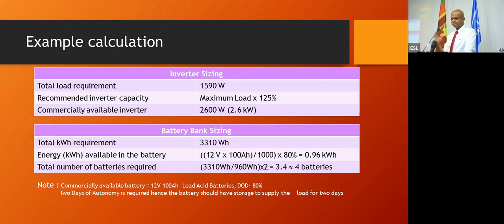Otherwise, you're going to have a lot of idle current, which is energy loss. So battery bank sizing, there are various ways of going about it, but for simplicity I've done a very simple way. Our total kilowatt hour requirement in terms of storage is 3,310 watt hours. If you multiply amp hours by the voltage, you get the watt hours.